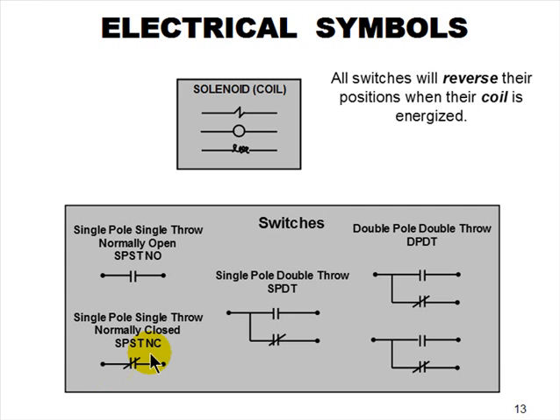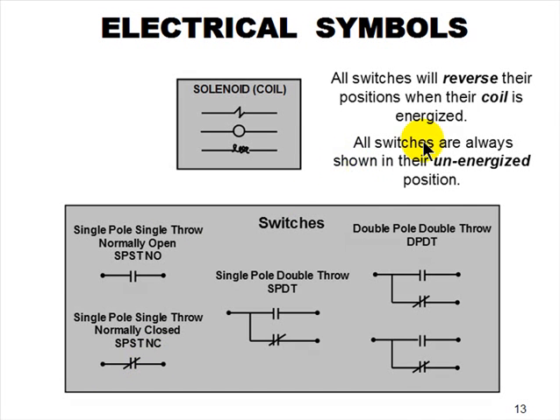All right, switch. That means unenergized positions. All switches are always shown in their unenergized positions. You have to envision, when you see this single pole, single throw, normally open switch, that when its coil gets power through it, and there's continuity in that coil circuit, this switch is going to change positions. But when you look at it on the plan, it's going to show open. Okay, that's the way they're all going to show. Here's single pole, double throw. I have 2 throws. I have 2 options. I can use this switch for normally open. So when the thing calls, this will close, that'll open. This is my other option.